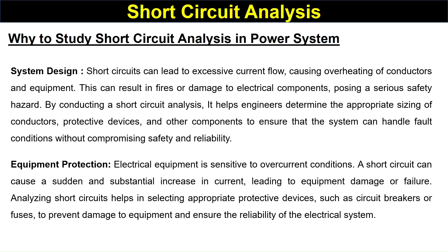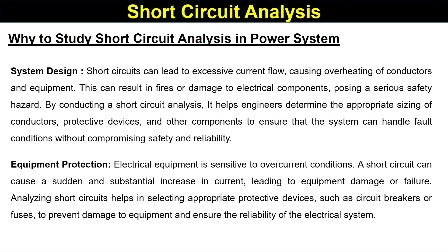The second reason is equipment protection. A short circuit can cause a sudden and substantial increase in current, leading to equipment damage or failure. Analyzing short circuits helps in selecting appropriate protective devices such as circuit breakers or fuses to prevent damage to equipment, so that the main component being protected is saved, and the protective device itself is also not damaged.